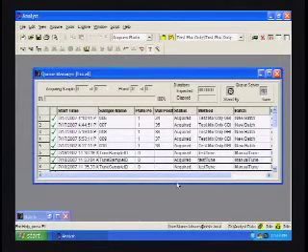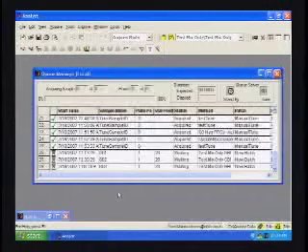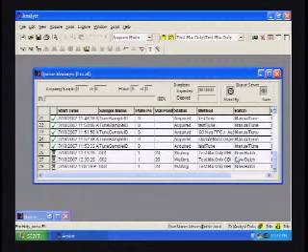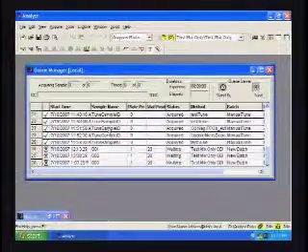So we can see our three samples here at the bottom. We'll maximize their pane. There we go. We've got a whole bunch of stuff in their queue. These three samples are, as the status indicates, waiting to be acquired. They're in vial position 20. And it is a new batch. So at this point, in order to get the sample test mix injected, we would click on the...